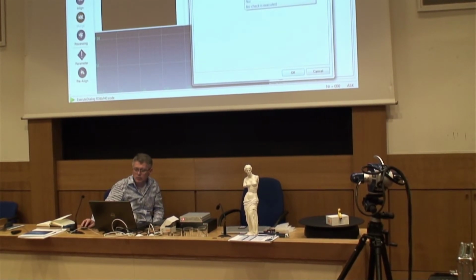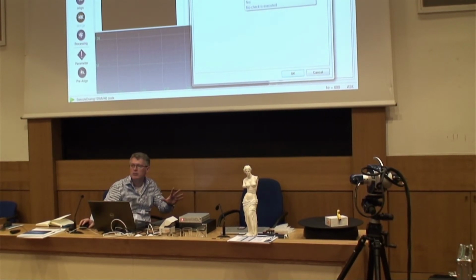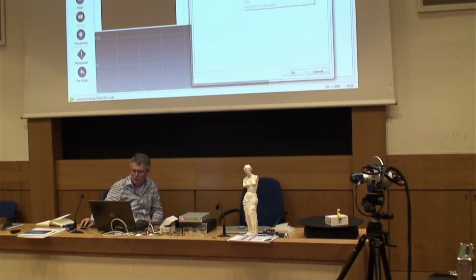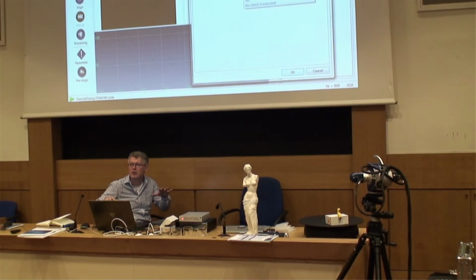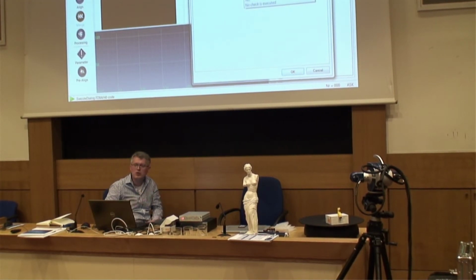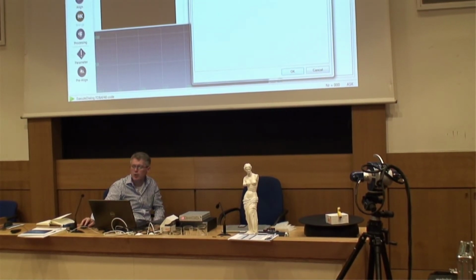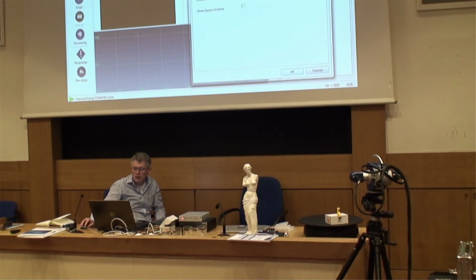Stability check, this was on. I don't know who recognized it this morning. The scanner was just standing for 20 seconds. So probably the stability check kicked in, saying, well, the ground is not stable enough, I stop scanning, I continue when I'm not shaking anymore. So we keep that on, because otherwise there would be blurred images, sometimes hard to detect. And now we have certain parameters, filters, we keep it standard, data masking. Speed up by using preview.